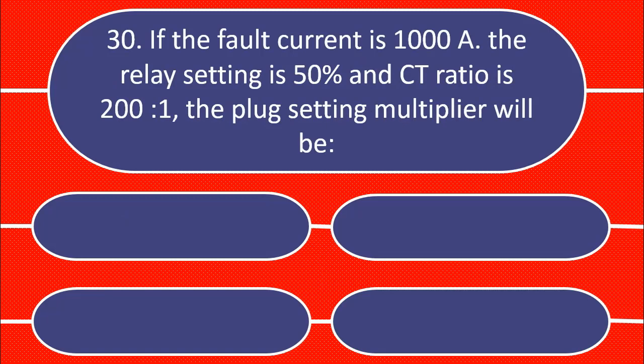If the fault current is 1000 Ampere, the relay setting is 50% and CT ratio is 200 is to 1, the plug setting multiplier will be.